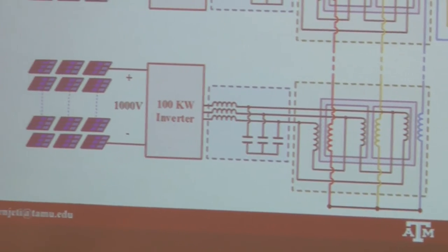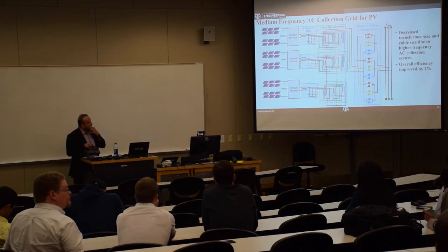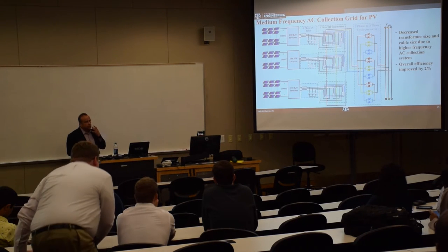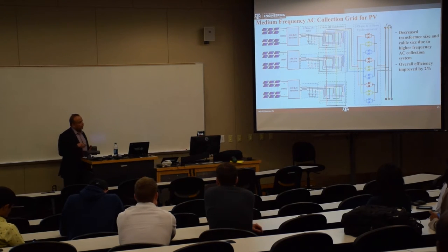We looked at the AC drives which they manufacture. They can operate actually easily up to 1 kilohertz sine wave. So you change that into medium frequency, and then apply the medium frequency transformer concept. And then on the secondary side, you're connecting them in series, essentially increasing their voltages as you keep going. You're getting higher and higher voltages. And then after that, you get a higher frequency AC here, and then that's connected to the 60 hertz through a regular line commutated cycloconverter.